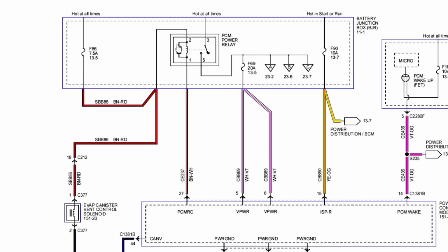Starting with the control side of the relay, you can see that on pin number 2, if we follow it out, it gets its power from fuse F86, which is a 7.5 amp fuse. That power coming in on pin number 2 goes through the coil winding of the control side of the relay, and comes out on pin number 1.